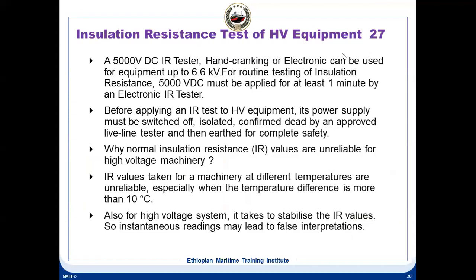The insulation testing of the high voltage equipments. Normally we use a 500 volt megger to measure the 440 volt circuit, maximum 500 volt megger. But in case of high voltage, a 500 volt megger won't do. You have to use a 5000 volt megger, because with insulation measurement you are impressing a high voltage across this insulator. For 440 volt systems a 500 volt megger is good enough, but for high voltage equipment you need a higher voltage, at least 5000 volt.